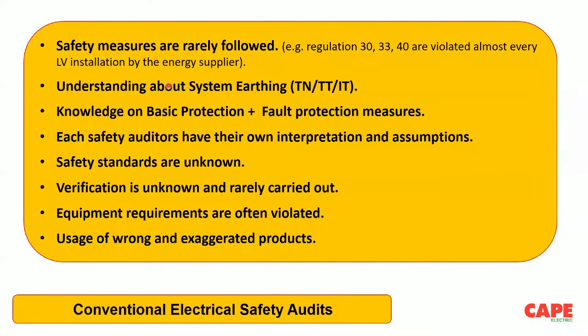So basically the problems are: safety measures are rarely followed. For example, regulations 30, 33, 40 are violated in almost all low voltage electrical installations. Guarding is not there. For the protective regulations 14, 15, 16, the earthed conductor from the supplier side is not available in most of the state governments. So these are actually attributing to a large number of accidents. Similarly, understanding about system earthing: TN, TT, IT. If you don't know what TN, TT, and IT are, you cannot do a verification. Earthing is not about putting hundreds of earth pits. Earthing is about the best way of making one of these system earthings and ensuring that all the safety measures are made. So most of the time, the auditors are very rarely aware of TN, TT, and IT systems.